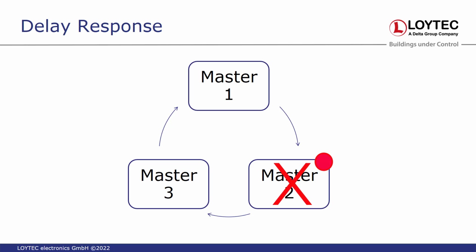If every node is responding fine, then one gives the token to the next, to the next, and this works fine. But if there are only a few nodes that are not passing on the token, then this slows down the whole network traffic. And I think this is the case. If you have these issues, you can check the statistics pages, like Hans said, and you would see that the token is lost and that this is the issue.